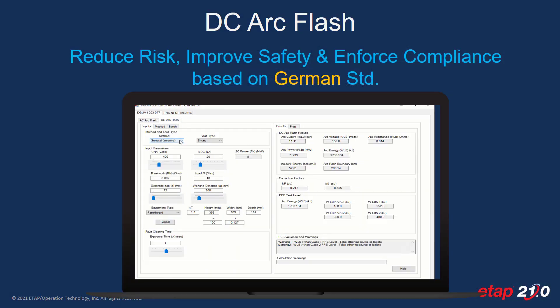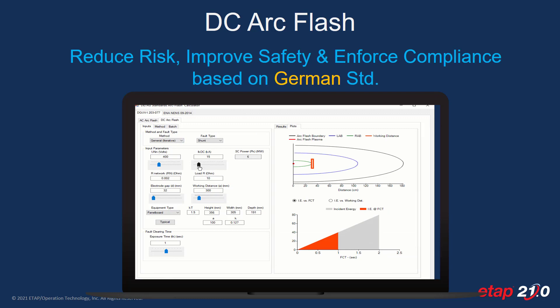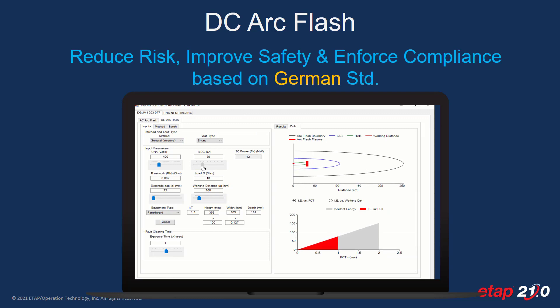Within the calculator you can go to the DC arc flash tab, where you have your two methods — worst case or iterative — and the shunt and series fault type options. As you change them, the results are dynamically updated, as are any of the sliders for voltage, current, working distance, and gap ID. We can dynamically change any of the input parameters for quick results and view plots as well.